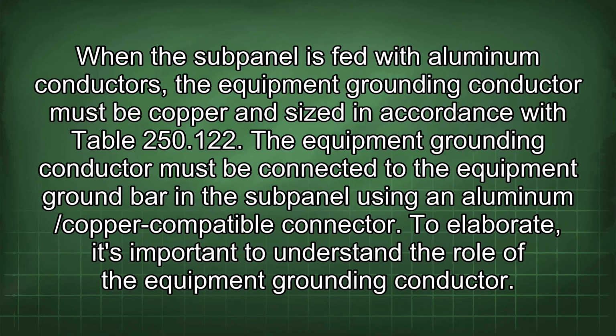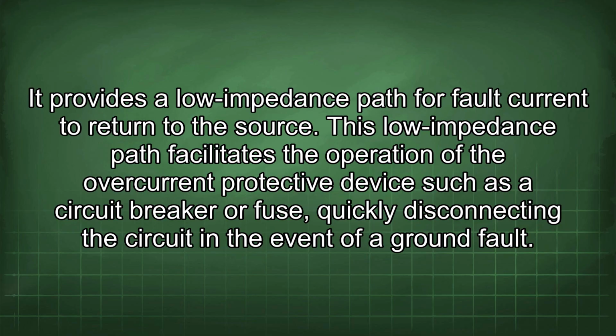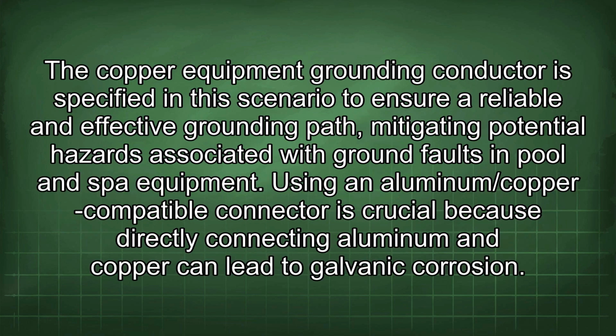To elaborate, it's important to understand the role of the equipment grounding conductor. It provides a low impedance path for fault current to return to the source. This low impedance path facilitates the operation of the overcurrent protective device, such as a circuit breaker or fuse, quickly disconnecting the circuit in the event of a ground fault. The copper equipment grounding conductor is specified in this scenario to ensure a reliable and effective grounding path, mitigating potential hazards associated with ground faults in pool and spa equipment.